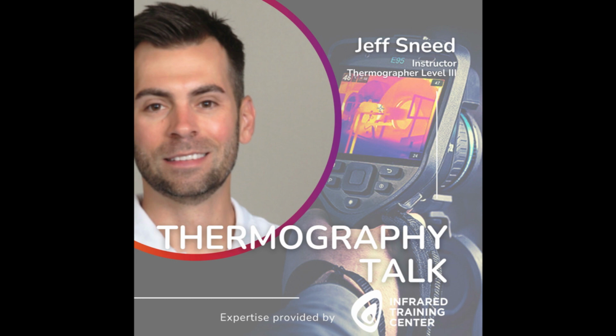We can be really far back in some cases. Now, this is very camera model dependent on how far you can actually be away versus the size of your target, but those are some of the things that we review in our infrared training center courses. The situation that you'll find yourself in is, you're either the person that's opening up the cabinet doors who is also going to be doing the thermal scanning. That can be a problem because you will be, when you open the door, in some of those restricted or limited approach boundaries. You're going to be really close when you open the door, but when you back up is when you've reduced that arc energy, when you get further back. So you're still going to have to wear a higher level of PPE if you're going to be the one that's opening the door, if you're within those working distances.